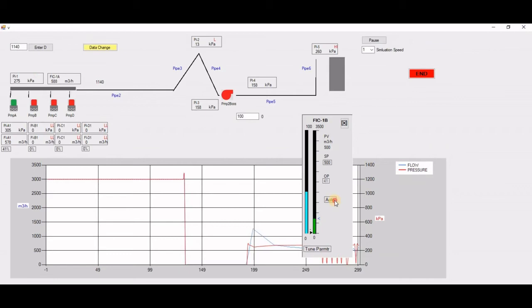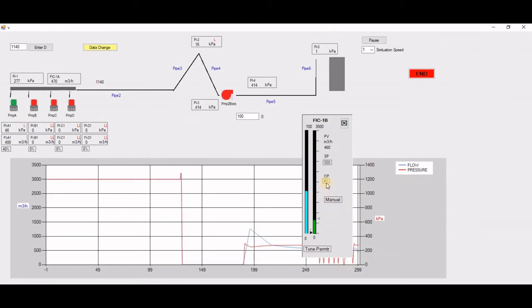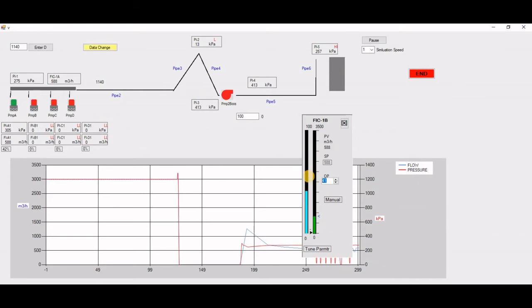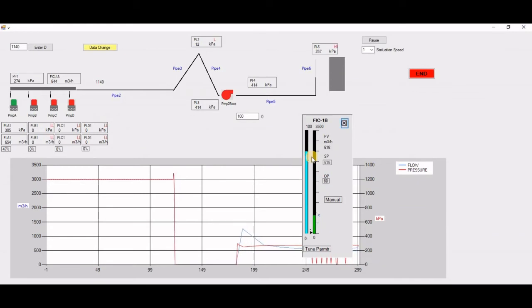I can change this PID loop into manual and I can change the output to 80 percent. You can see there is a delay between my command from the controller until the pump actual speed reaches it.